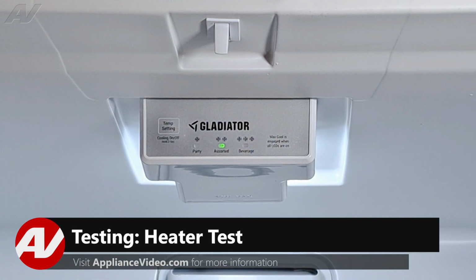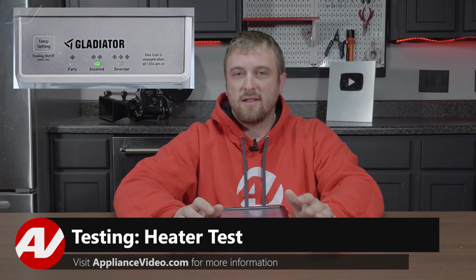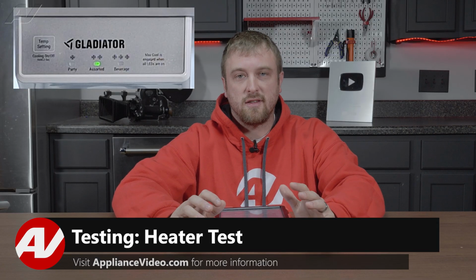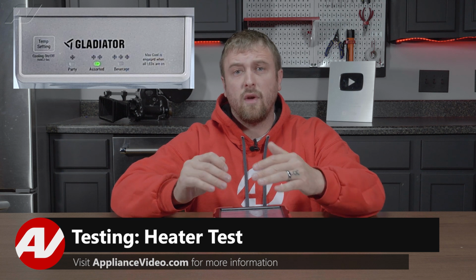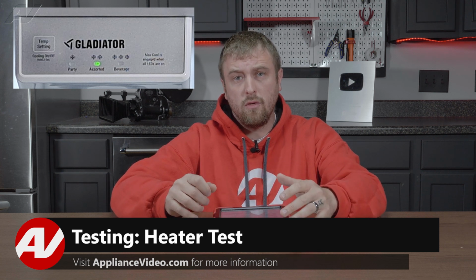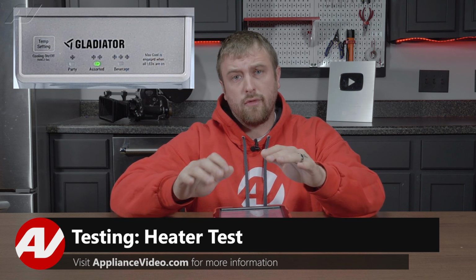And this is going to be a heater test. The heater test is built to test out the defrost system. Like I was saying before, we need the fan in order for the unit to cool. Well, this unit is a self-defrosting unit, so every couple of hours a heater turns on, melts the ice in order for you to have proper airflow. If the heater is not turning on, it will build up that ice all the way up the top, and the air will no longer circulate in the unit, thus causing cooling problems.